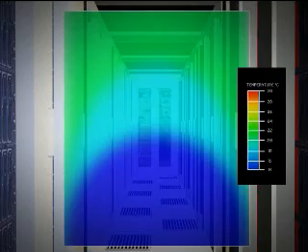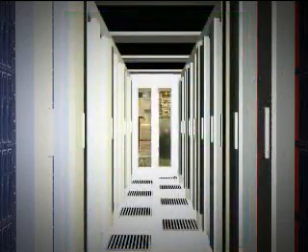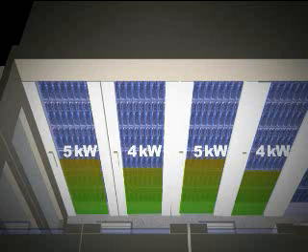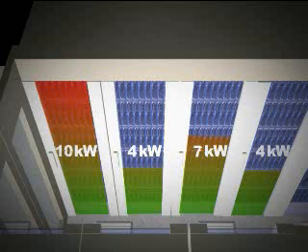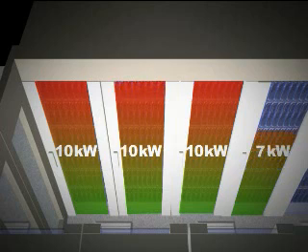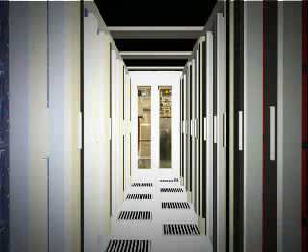Depending on the installation and the servers, the CRAC air outlet temperature can be raised, therefore reducing the activity of the chiller and in turn improving your mean time between failure. As a byproduct of encapsulating the cold aisle, you can also increase your power consumption per rack, typically from 5 kilowatts to approximately 10 kilowatts per enclosure. This now enables Rittal to provide a low-cost, lower-footprint, medium-density data center with a very simple mechanical add-on.